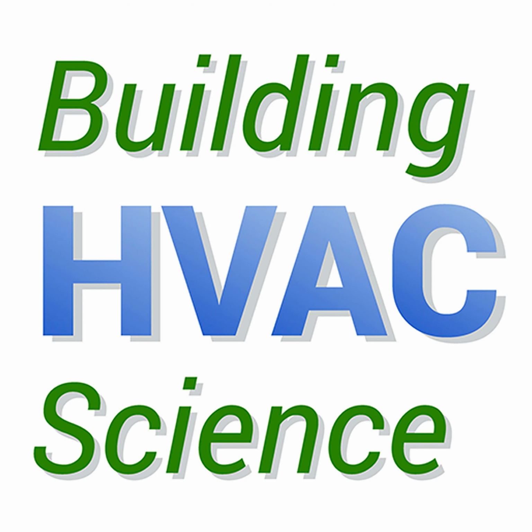Thank you. That's maybe a good point to compare to some other technologies. The way we think about it is liquid desiccants are great at most of the market, and this is a little bit on the very, very low end. If you want to get down to something like lithium-ion battery manufacturing, these are at 1 or 2 grains per pound, super, super dry air, like a negative 20-degree dew point. Technically, liquid desiccants can get there, but not this system. You'd really need an ammonia chiller to cool that desiccant down to around negative 10 degrees. So we're not doing that; there you'd go with a solid desiccant. But for anything down to that 35-degree dew point, which is the majority of the market, we're able to meet customer needs.